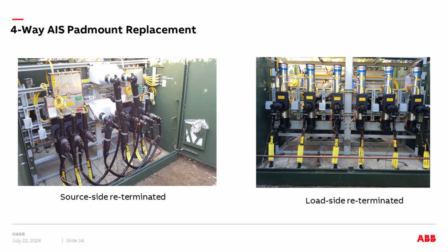Here's another view, source side re-terminated, and on the right, the load side. I showed that picture at the beginning with the spread. So again, it just points to, with modular components, with cable bus, with bus jumpers, with different kinds of parts in our toolbox, I would say it gives us the flexibility to match existing locations in what would otherwise be difficult to accomplish without having to dig out the pad or splice in new cables.